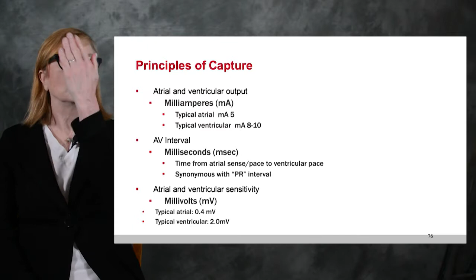Principles of capture. And there are two really particular ones that are important. First of all, the output, which is the amount of stimulus that I'm delivering into the chamber. Typical for the atria to be at 5 milliamps, and typical for the ventricular impulse from the pacemaker to be at 8 to 10 milliamps.